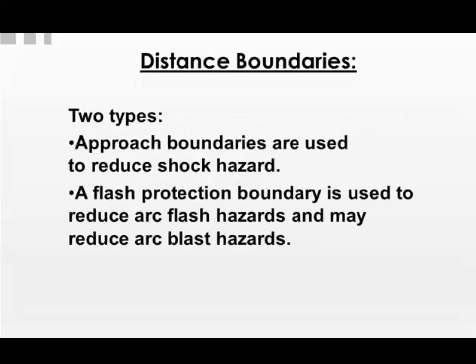So I touched on this, but let's get into distance boundaries because this is an important part of the process. So there's two types. You have approach boundaries, which are used to reduce shock hazard, and a flash protection boundary, which is used to reduce arc flash hazards and may reduce arc blast hazards. Now keep in mind, the arc flash is the initial event and the blast is the explosion that comes out. You'll hear those terms interchangeably. They are two different things, but they certainly tie together because one happens right after the other and almost simultaneously.